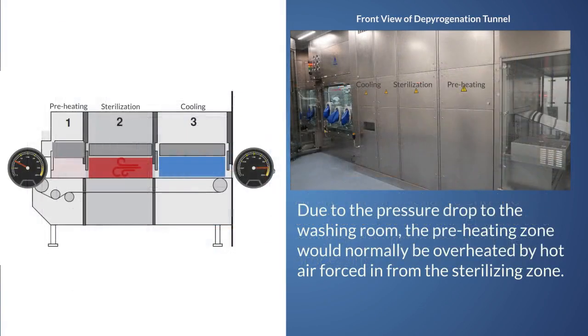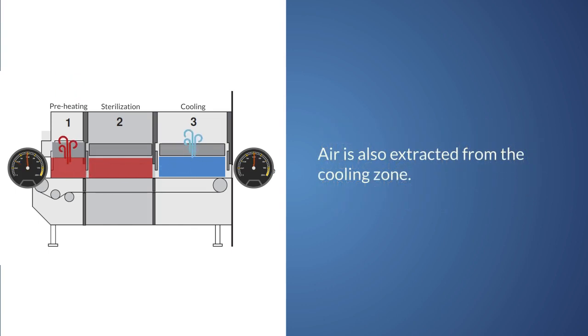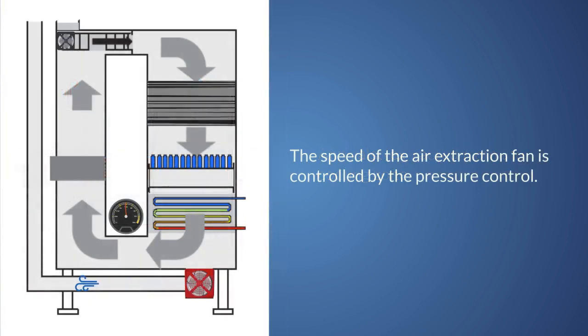Due to the pressure drop to the washing room, the preheating zone would normally be overheated by hot air forced in from the sterilizing zone. In order to reduce the pressure difference between the isolator and the preheating zone of the tunnel, air is extracted from the preheating zone. Air is also extracted from the cooling zone. The speed of the air extraction fan is controlled by the pressure control.